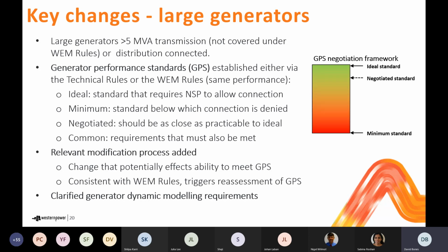The ideal standard represents a level of performance that if you reach that level, then the network service provider would not be entitled to refuse connection on the basis of your ability to deliver that particular technical requirement. So that's a condition that's going to be sufficient under all conditions for connection with respect to that technical requirement. The minimum standard, on the other hand, represents a level of performance that might be appropriate in some, but not necessarily all circumstances. So you could imagine what might be appropriate for connection in one particular part of the network, or with one particular technology, may not necessarily be appropriate everywhere.